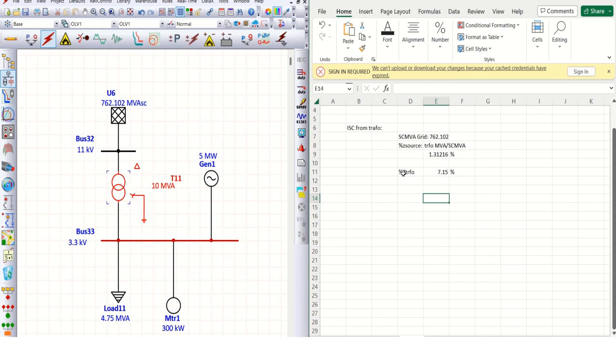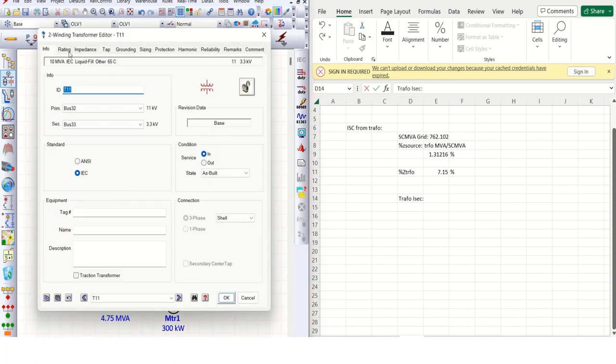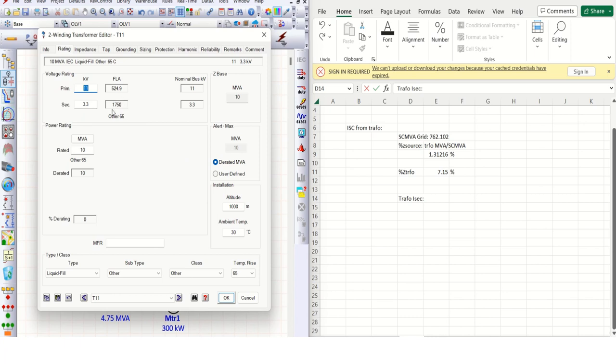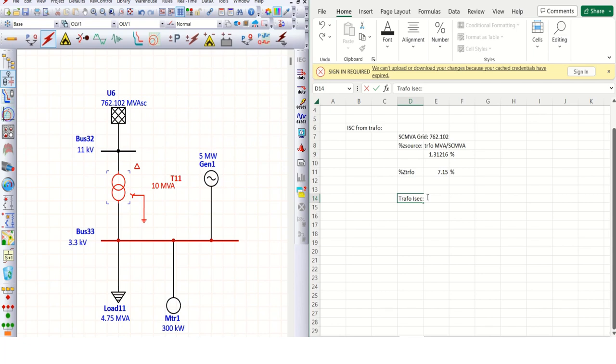Now you can simply calculate ISC from trafo, that is the trafo secondary current. Now what is the trafo secondary current? Again, go back to this transformer, check the rating page. 1750 is the trafo secondary current.